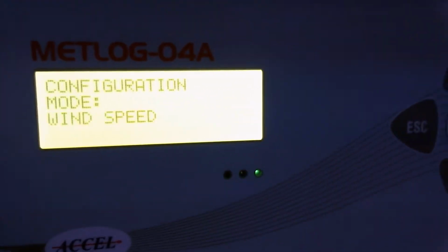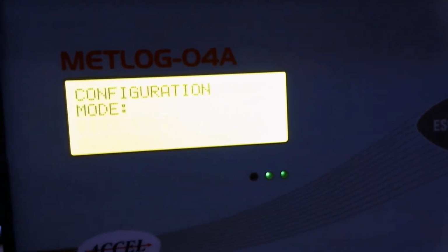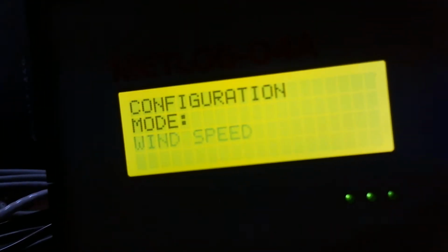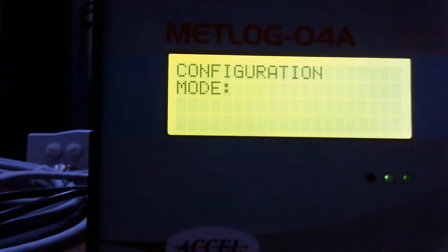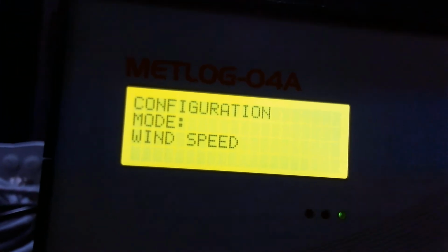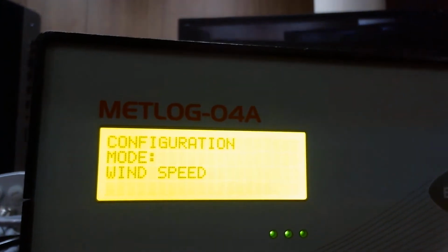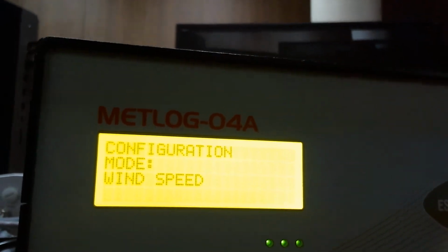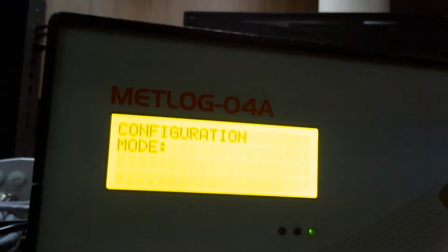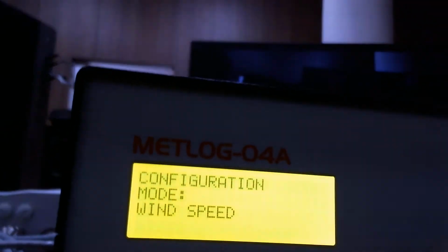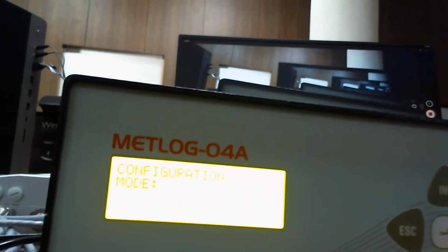So now all sensors, means pressure sensor, wind sensor, then your temperature humidity sensor, then your cloud sensor, these are to be configured. Configured in the sense which communication port you have connected, whether you have connected to COM1 or COM2 or COM3 or COM4. Then each sensor has a particular baud rate, because our sensors are sending the data serially.